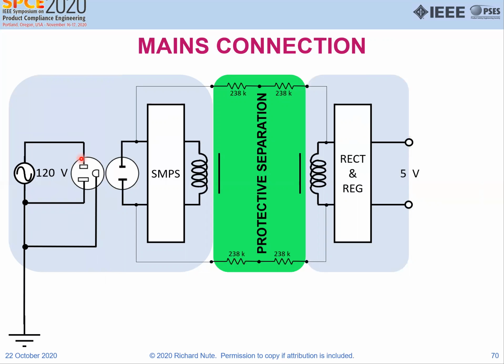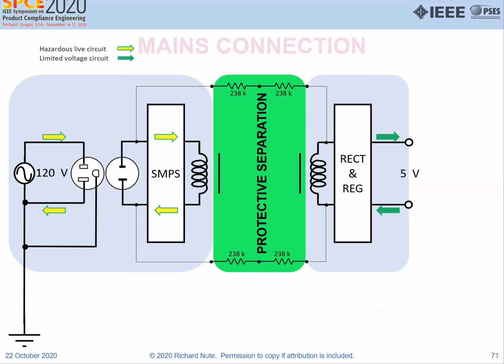And here is the primary and the rest of the primary circuit, 120 volts. And this is a 2-wire system. Well, it doesn't connect to the ground. So the primary circuit, the hazardous live circuit, is this one. It goes from 120 volts, into the switching mode power supply to the transformer, and returns back to the 120 volts. The output, here's the 5 volts output to the load, wherever the load is, and returns that way, and has protective separation.